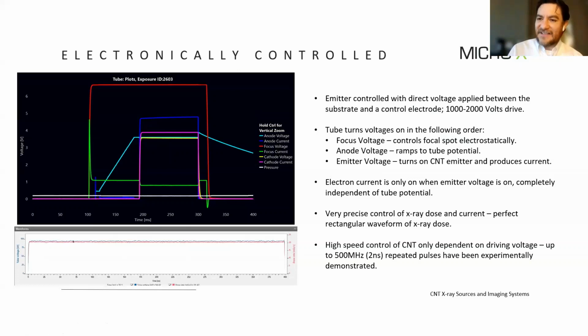And that gives us not just precise control of the dose, and the dose through the entire pulse, but it also gives us the ability to turn on and off the X-ray tube very quickly, kind of like a grid control X-ray, only there's no wasted energy in this. So we've actually demonstrated in the lab that we can turn on and off our electron emitter up to about 500 megahertz, 2 nanosecond pulses, repeated, consistent pulses. And we only went that fast because we couldn't find a device to measure that. We had to use a multi-channel plate detector to validate that we were actually getting X-rays that fast.